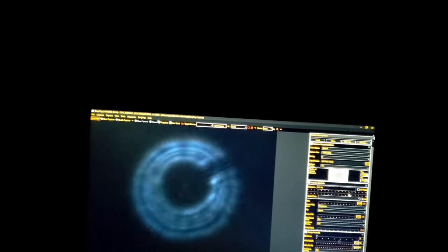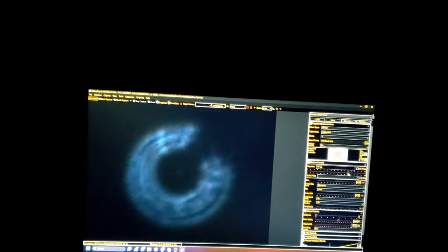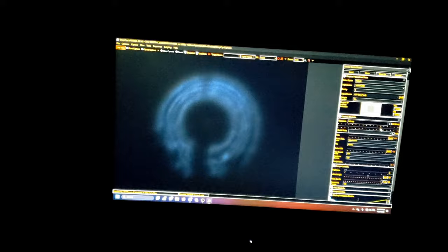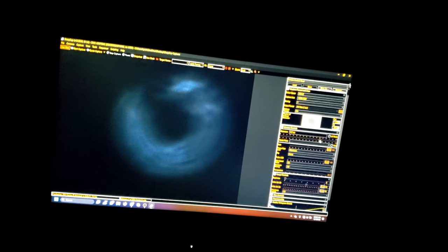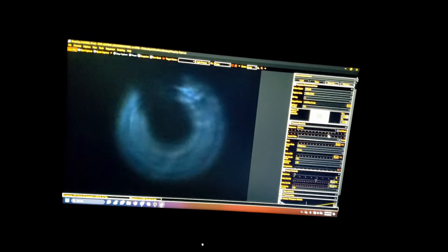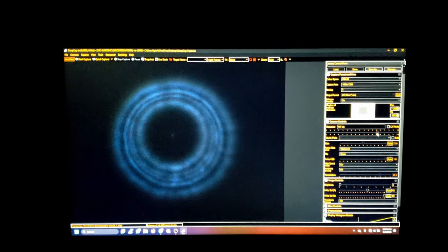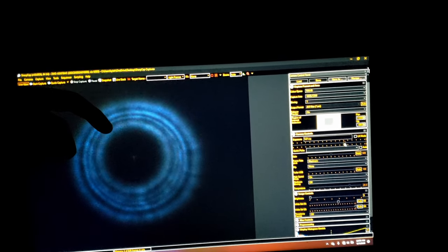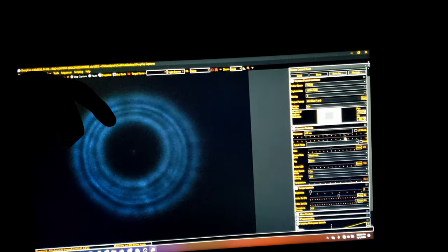Now, the proper next question is, how do we know which one to adjust? And the answer to that is actually that I'm just going to take my hand and stick it in front of the telescope, just radially towards one of those screws on the end. You can see my finger jutting into the frame right there. So that's one screw coming out to the top side there, another screw coming to the bottom, and then a final screw coming kind of over on that side. So that final screw that I just touched is associated with that little shorter area there. So we're probably going to adjust that, since it should be the easiest to get us back into centering.